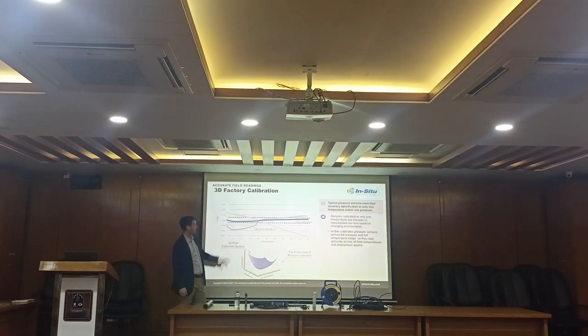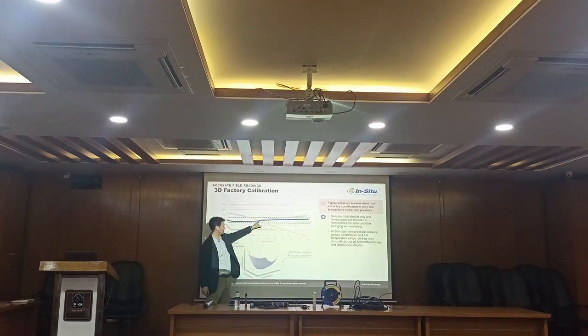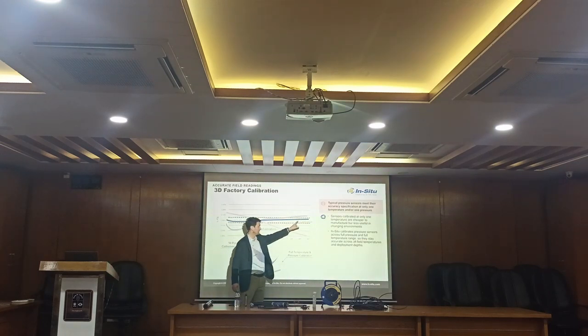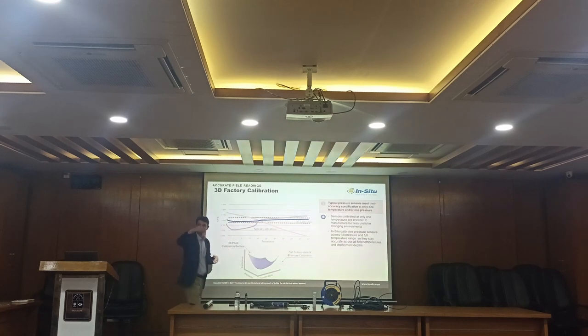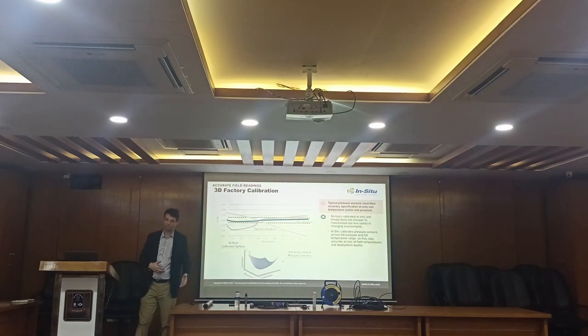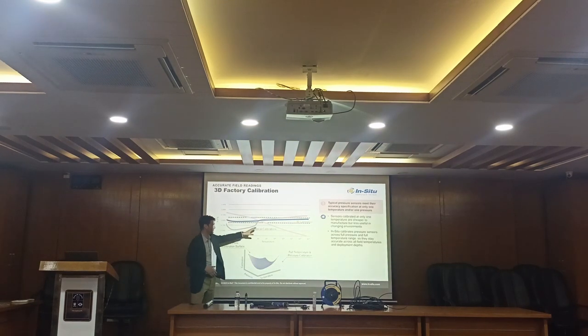Like I mentioned before, typically we find it's right about 20 degrees C where everyone's really accurate. This blue line here, this is us. We maintain that within 0.05% throughout the full temperature range that we have. These other lines are not just scribbles we put on a graph, they are actual data from other manufacturers. And no, I'm not going to tell you who they are, because that's not right.